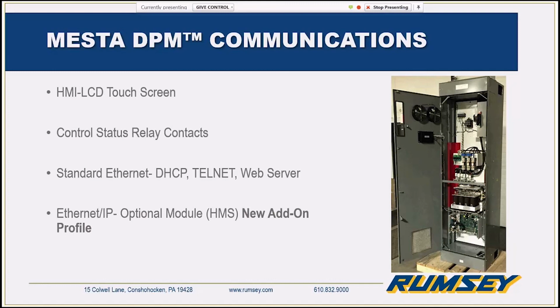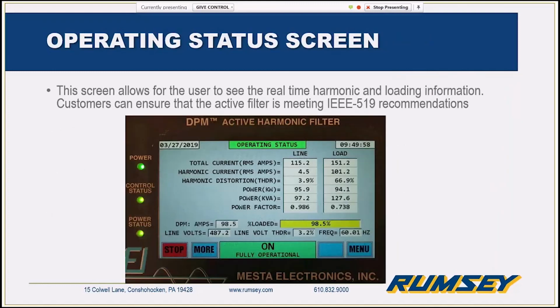So here's a look at our operating screen. As you look through this, you'll see we're pretty much a full power monitoring device. The load column is before correction and the line column is after correction. So you'll see this is a 100 amp filter correcting from about 67% THD down to 4%. And you see the RMS drop in current from 150 to 115.